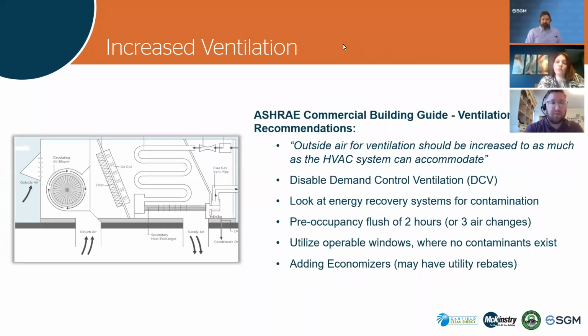Next major strategy is going to be increasing the ventilation. And what we're doing here is we're diluting the air with outside air. So we're exhausting building air and we're mixing in fresh air. ASHRAE is essentially recommending as much as you can. That typically is limited around 30 to 40%, sometimes more, sometimes less, before your system can't meet capacity and cool and heat the space. And it's really dependent on the system.